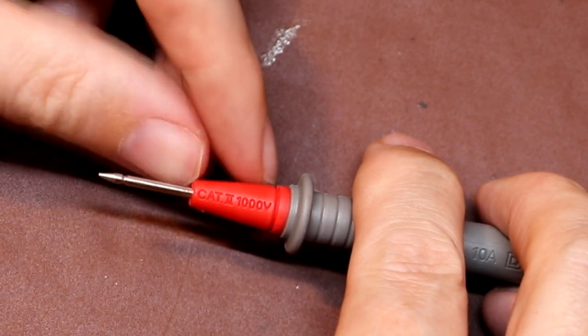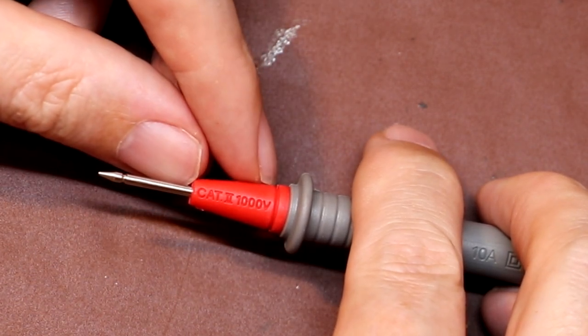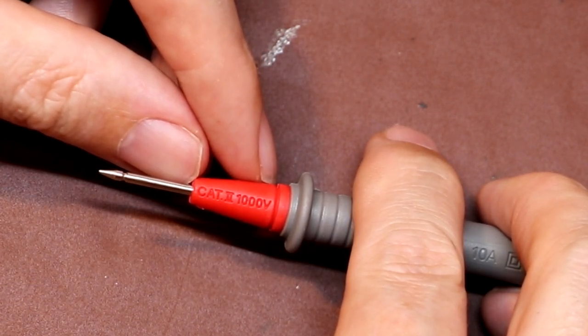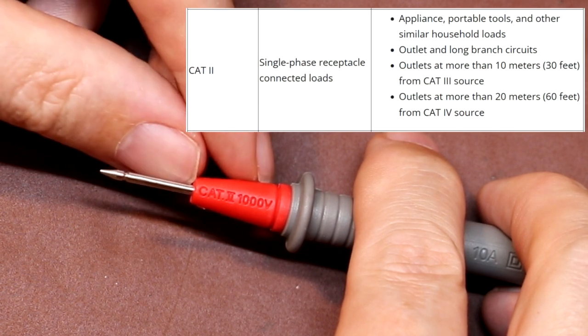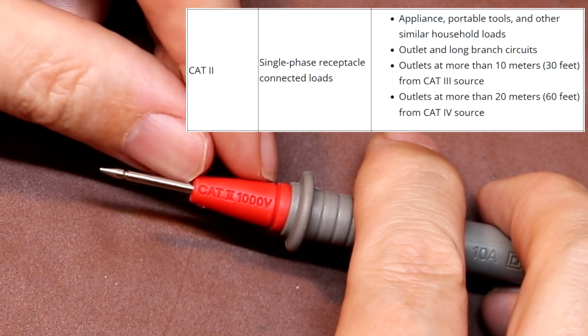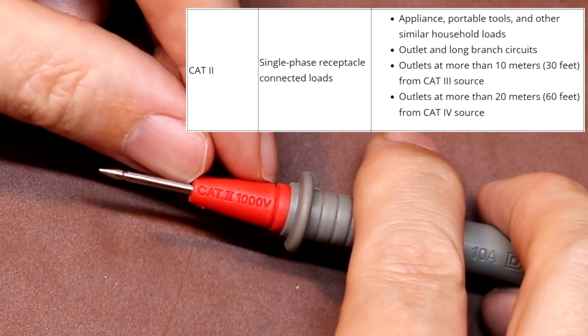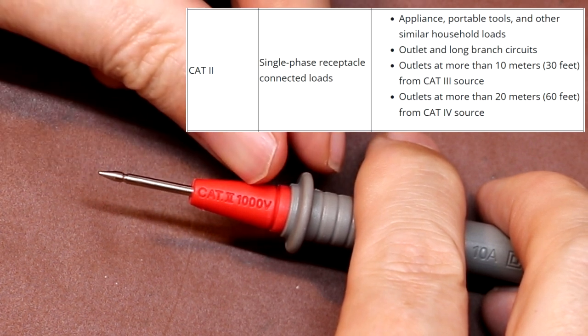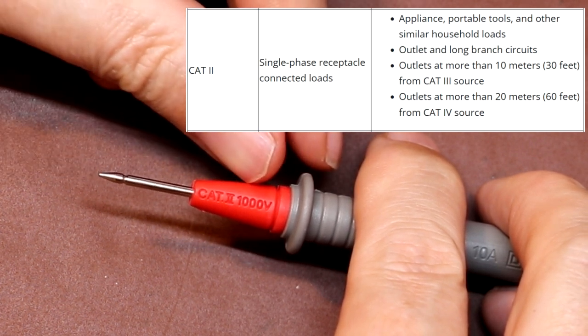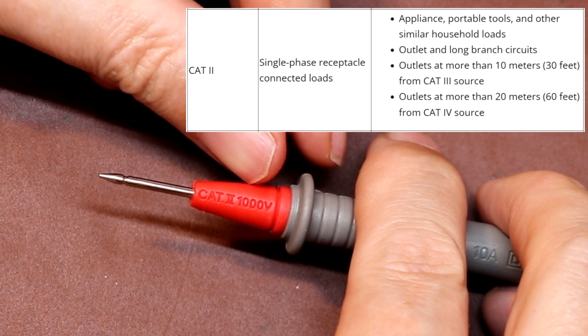Now I can also see that we've got category 2 1000 volts stamped into the handle of the probe. At first sight, a category 2 rating doesn't appear particularly good. A lot of people don't seem to really understand these category 2 ratings, and a lot of people just look at the voltage rating. Now the voltage rating I don't really consider that much. Let's face it, these are made from plastic. Anything made from plastic is going to have a good high voltage rating.